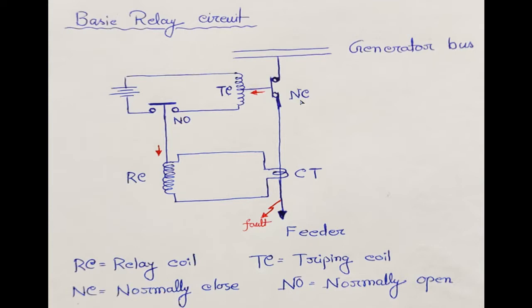Now let's see what happens in case of fault. Now this is the symbol of the fault. If a fault is present in this position, as it's a short circuit fault, the current increases rapidly, and this increased current is also reflected in the CT secondary. Now the CT secondary and the relay coil also carry more current during the short circuit fault. As the relay coil carries more current during the fault, the electromechanical force also increases. Now, this increased force is able to move the plunger in the downward direction.